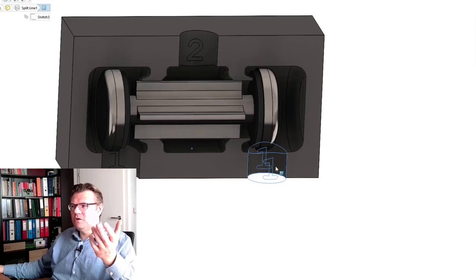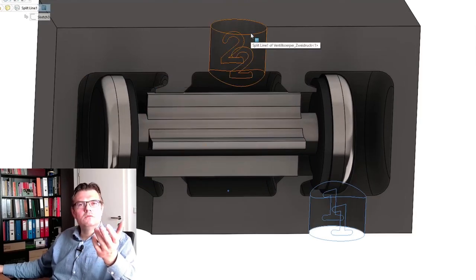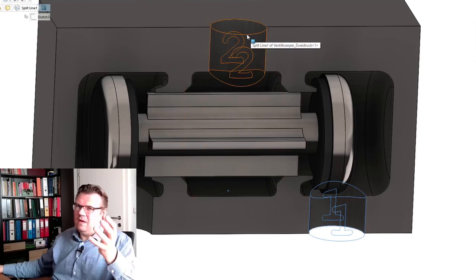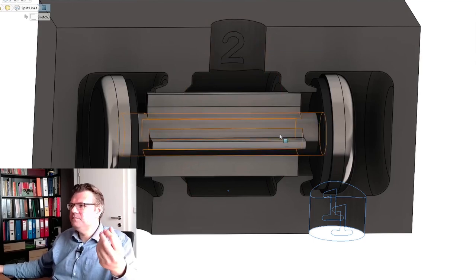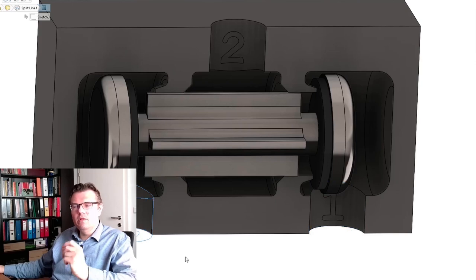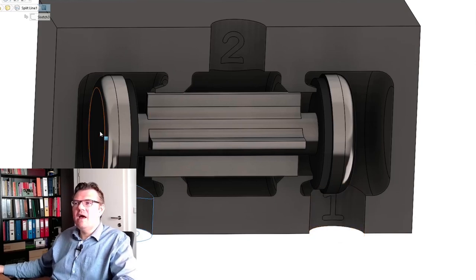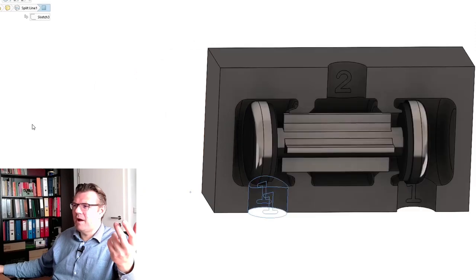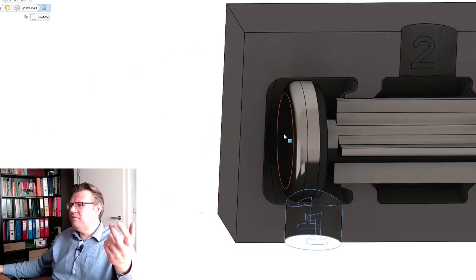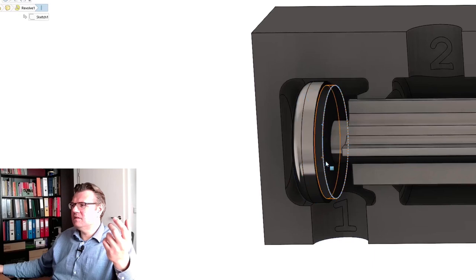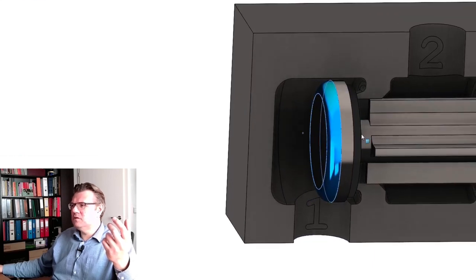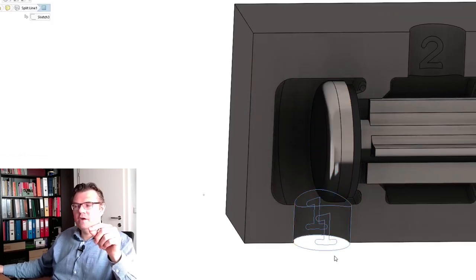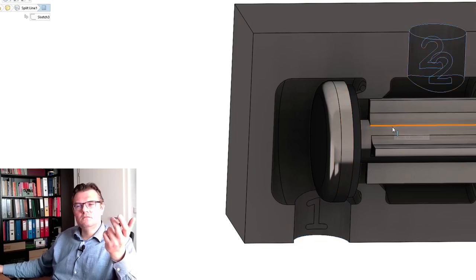So if I apply pressure here, here is no pressure. Maybe short, but not really. If I apply only pressure here and here no pressure, I have the same situation on the right side. So the force on this side of the piston is higher than on this side of the piston because of the rod, and we will move in this direction. If I have here pressure, here will be no pressure.